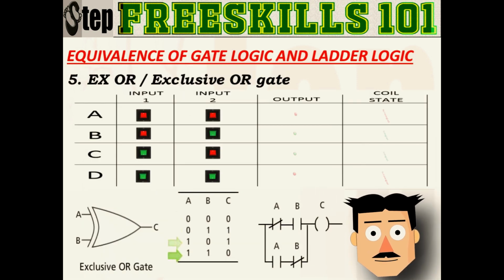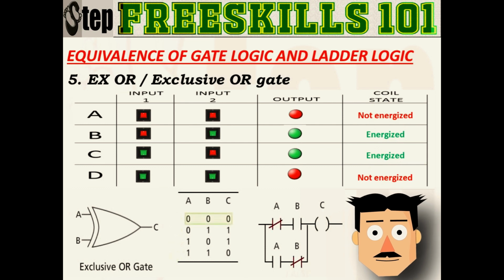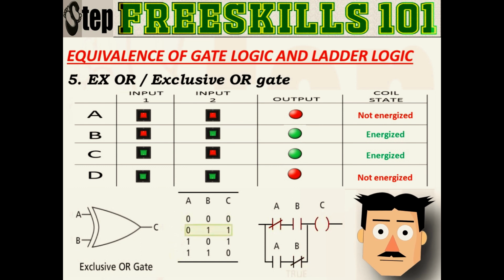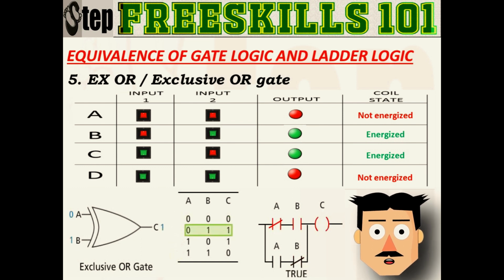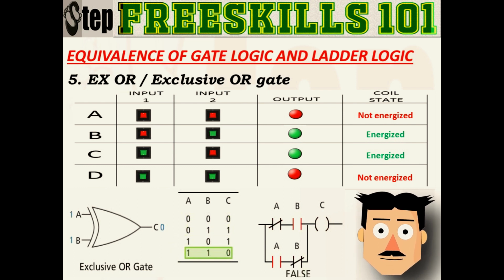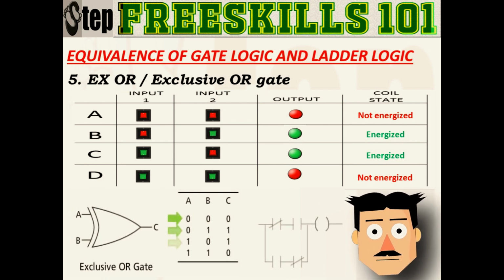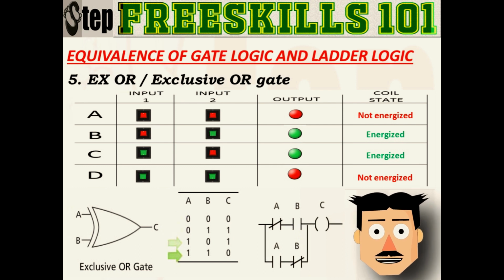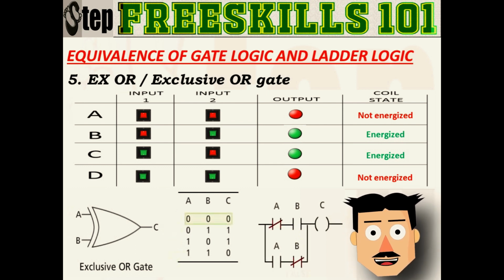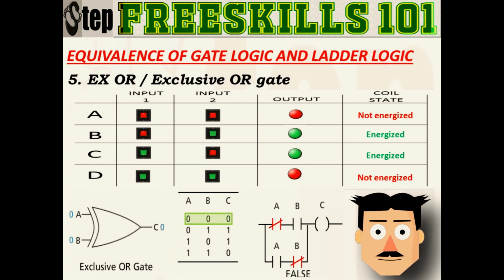Five, exclusive OR. In the exclusive OR gate, only one of them must be on in order to energize the output. If both of them are in the off state or on state, then the coil output is de-energized. This is used when you don't want two things to run simultaneously, or you want to run process 1 and 2 alternately.